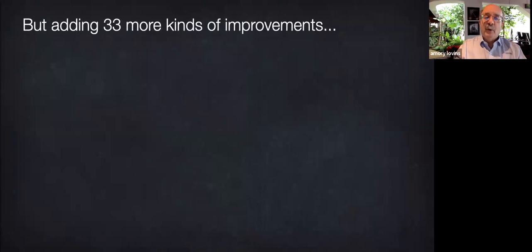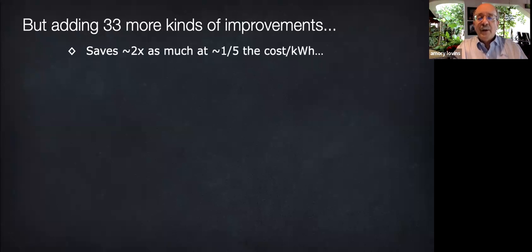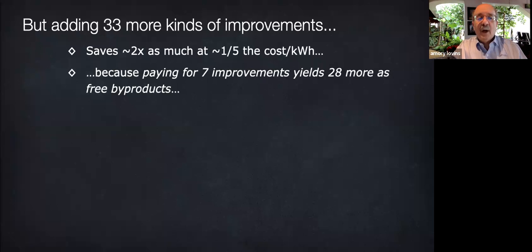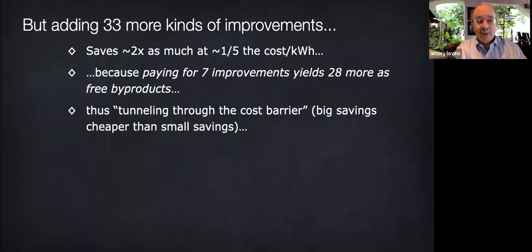But asking which efficient motor to buy misses the bigger picture, because that standard two-measure retrofit, replacing IE2 motors and adding ASDs, captures only about half the savings available from a whole system approach to the drive system alone, without improving the pumps and pipes or the fans and ducts or other downstream equipment. In other words, our whole system approach doubles the savings and cuts the cost per saved kilowatt hour by about fivefold by sequencing not just 2, but 35 kinds of improvements, thus tunneling through the cost barrier.